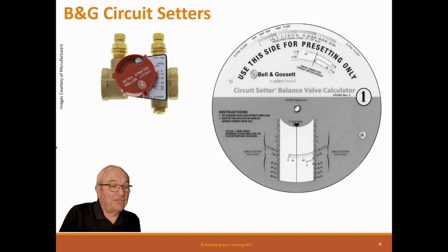Because you actually have to calculate the entire pressure of the system at every single valve. And the inlet pressure is different based upon the pipe characteristics. You have to actually go through an engineering exercise to do this. You might even have to do a Hardy Cross loop calculation if you have any loops. I mean, it's a tremendous amount of work that you and I are not going to do, I guarantee it. Now, if you have one valve, sure, no problem, because you can tell what the inlet pressure is going to be, but if you cannot, it's hard.